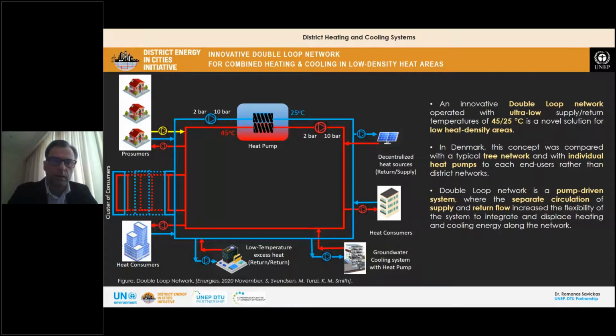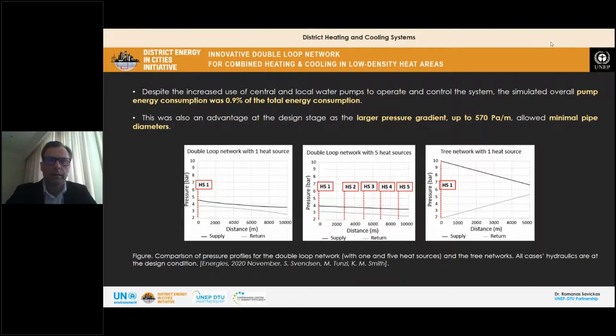So integration and dispatch of heating and cooling energy becomes much easier. And you can see in this picture the main idea and model of this double loop network, and all these flows, supply and return flows, are separated and can flow in different regimes. Despite the increase of central and local water pumps to operate and control the system, energy consumption was about 1% for pumps from the total energy consumption, and this was also an advantage at the design stage of a larger pressure gradient related to pipe diameters. And you can see in the picture the profile for the double loop network and for the tree network, and what makes the difference between these networks.